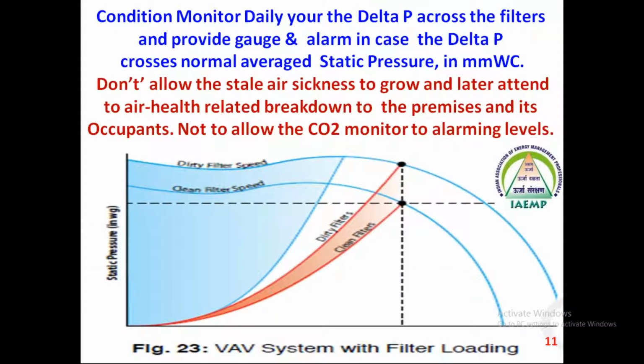This pascal is important not only in the engineering industry or textile industry or any other industry, but it is very much important in the HVAC industry. Because of this COVID situation, indoor air quality is more critical now. If the blower is getting choked, that is, if the HEPA filters, high efficiency particulate filters used in the blowers, are getting choked, automatically so much pressure drop will happen across the blower. The pressure builds up across the blower, which means the flow comes down. So monitoring the pressure across the HEPA filters in the blower is important to achieve better air changes within the air conditioned premises.